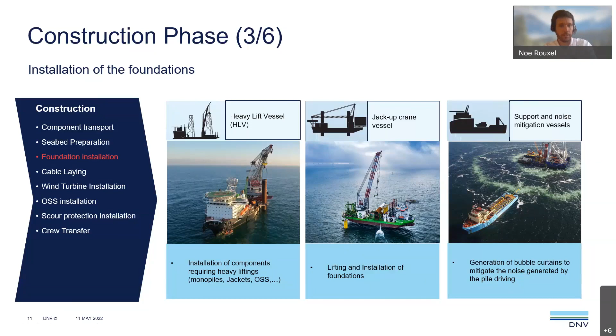The next operation is cable laying. There are two kinds of cables: inter-array cables and export cables. The inter-array cable links the different wind turbines to each other and to the offshore substation — typically a 66 kilovolt cable. The export cable connects the substation to shore, and is usually a much higher voltage, typically 220 kilovolt or even higher if it's HVDC.